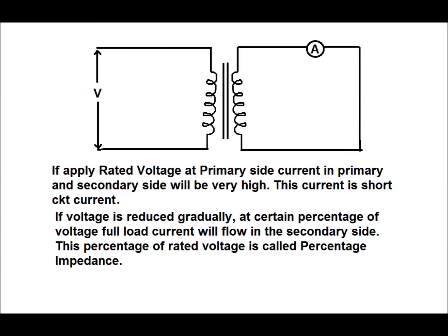In this diagram of the power transformer, a primary voltage is applied in the primary side and current is measured in the secondary side in short circuit condition of the secondary side. Rated voltage is given in the primary side and the measured current is very high — this current is the short circuit current. If the voltage is gradually reduced from the rated voltage, at a certain percentage of the voltage, full load current will flow in the secondary side. This percentage of the rated voltage is called the percentage impedance of the transformer.